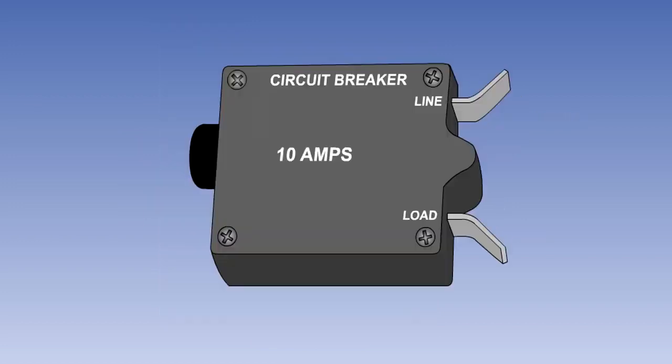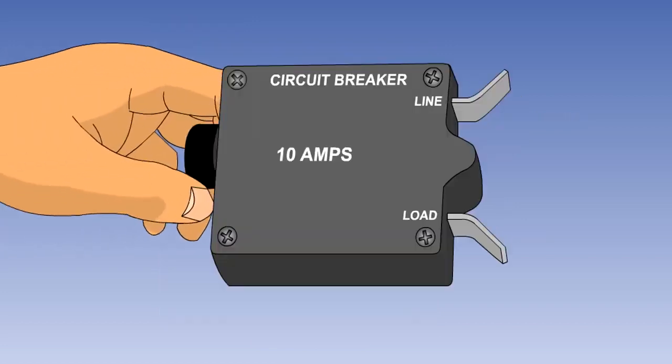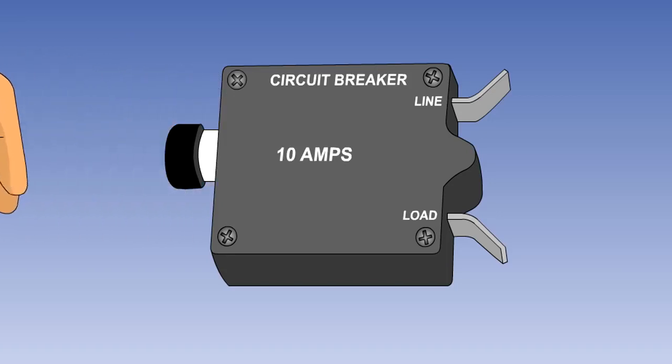If a circuit breaker has been pulled for maintenance purposes, then a clip with a red flag attached is affixed to the shank, to warn personnel not to reset it.